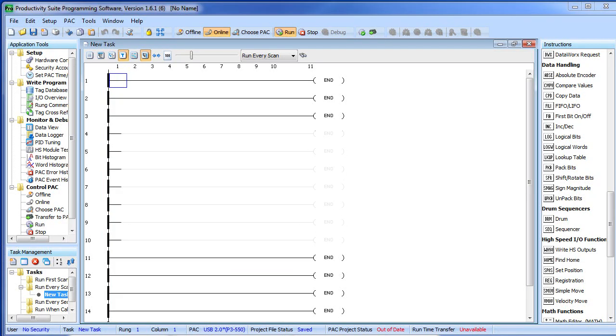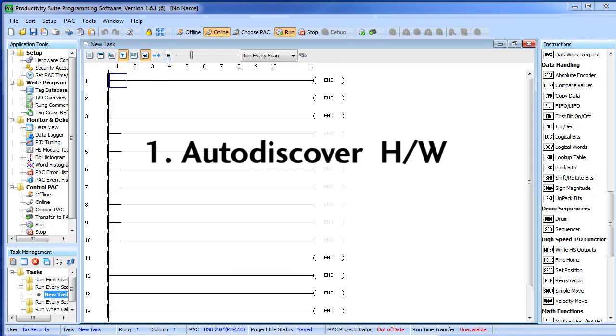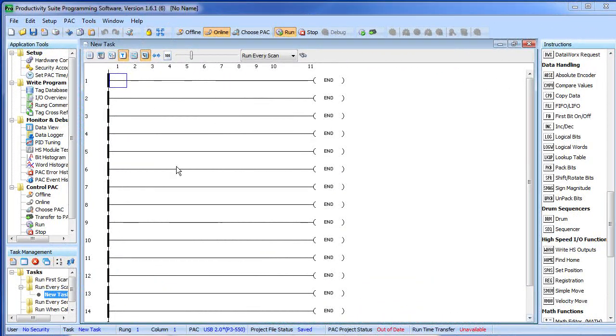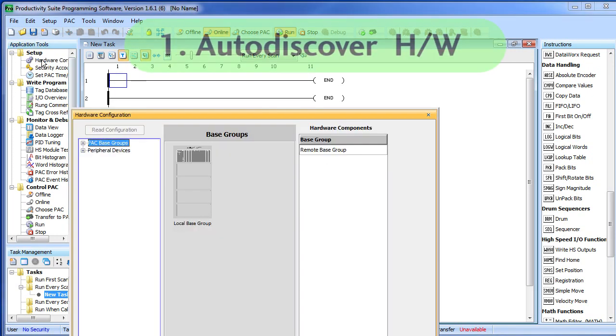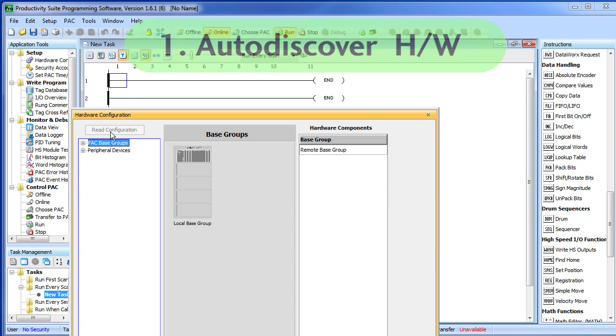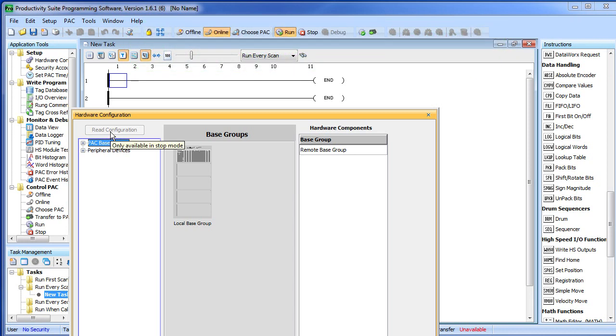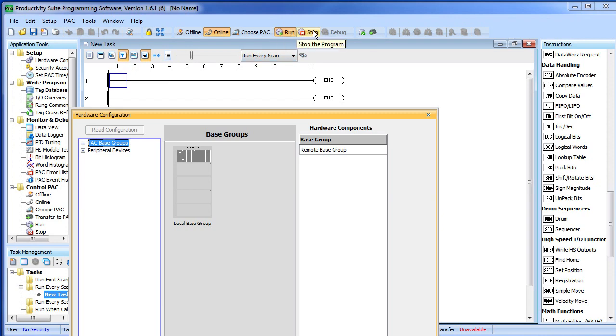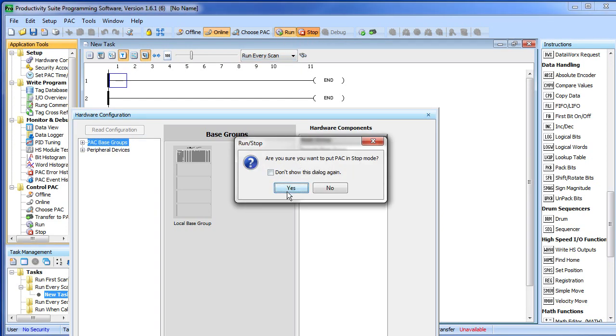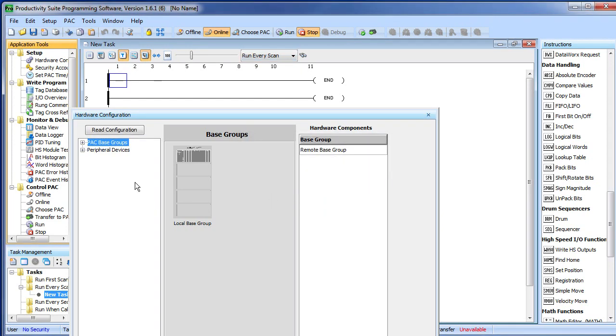To get going all we do is auto discover the hardware, configure the high speed output module and use it. Here we go. Here we have a new empty project and we are online with the controller. We will just double click on the hardware configuration and we want to auto discover that configuration by hitting this read configuration button. Notice the little yellow note that pops up when my cursor hits that button. It says this button is only available in stop mode. In other words I must be in run and sure enough I am, so let's go ahead and put it in stop mode. Yes, I want to do that. And now my configuration button becomes available.